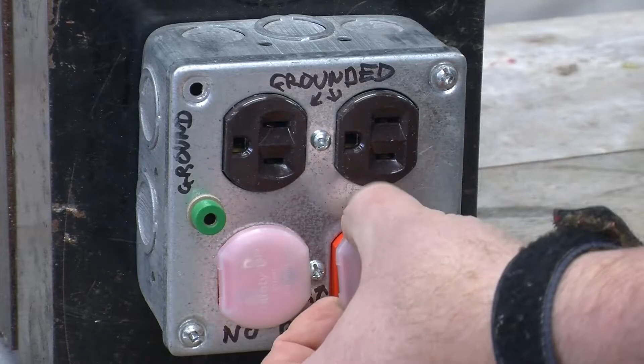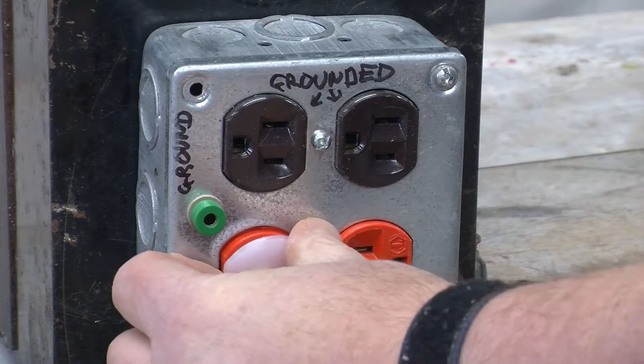So in those types of situations, after thinking about the situation and what device is under test or being experimented with or prototyped with or being tested after manufacturing, you have to decide whether the situation calls for a grounded or ungrounded connection. And what I usually do is cover up whichever set of outlets I'm not planning to use for a particular situation, so that I don't accidentally plug the device into the wrong one and give myself a false sense of security.